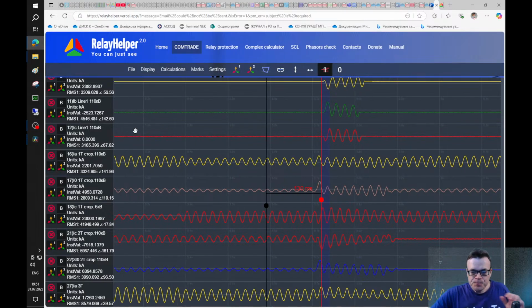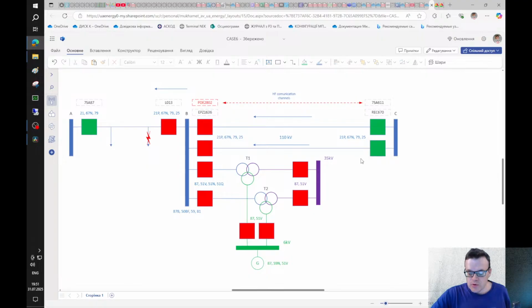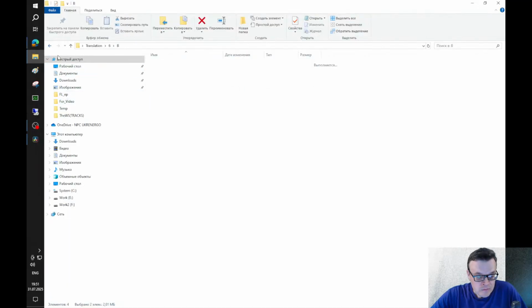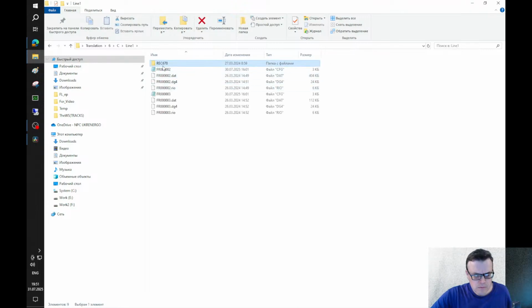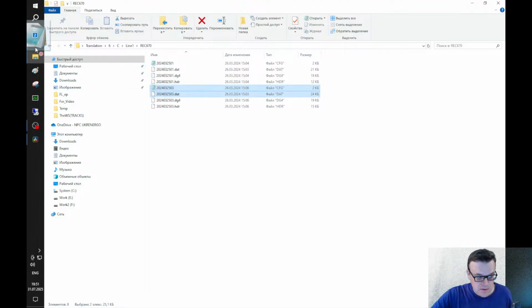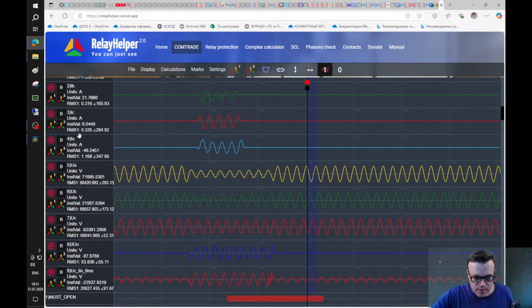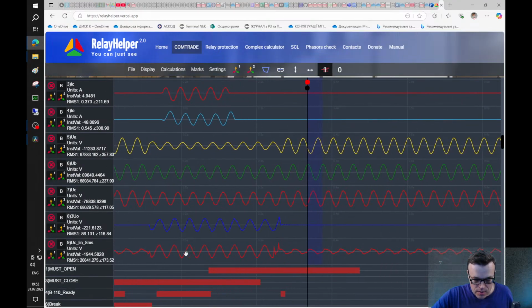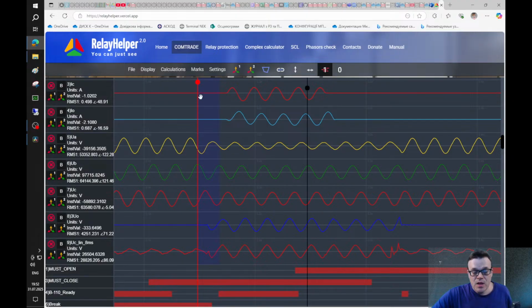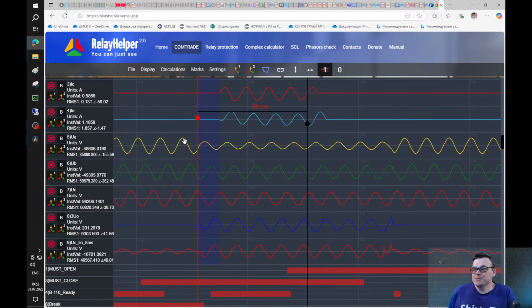Okay, to describe what happened, we should look at the substation C protections, and not the protection itself, but the BCU unit. So this first event is the first trip, and this is the trip during SOTF function work. This channel on the bottom is from a voltage transformer used usually only for the purpose of the synchro check.